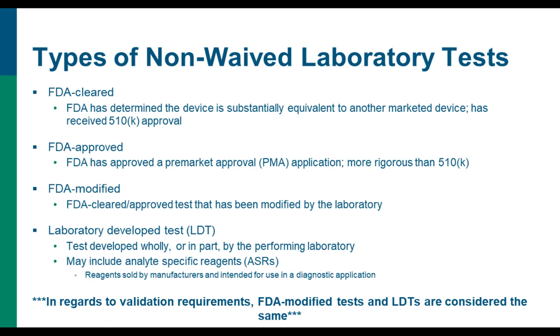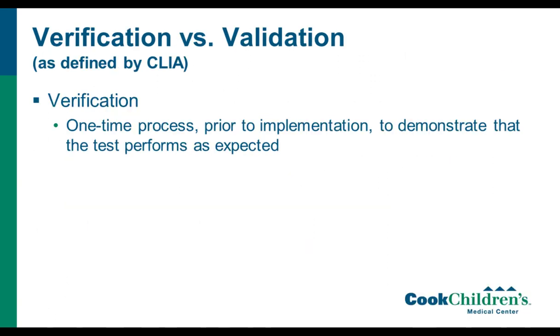And in regards to validation requirements for what we're concerned about in the lab with bringing in new tests, FDA-modified tests and LDTs are considered the same. So I've had people tell me or try and argue in the past that because the test was FDA cleared, it's okay, they don't have to do as stringent of a validation as a laboratory developed test. But actually, as soon as you modify it, it becomes off-label and treated like an LDT, and we will talk about that as well. So let's define verification and validation.